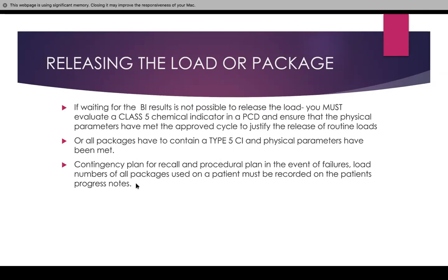There also has to be a contingency plan for recall and procedure in the event of failure. If a sterilizer is showing an error, physical parameters have not been met, or anything is not passing, we have to have a contingency plan. We have to recall all the instruments, see what the load number is, and see where it was used or if it was used. The load numbers of all packages used on a patient must be recorded on the patient's progress notes.